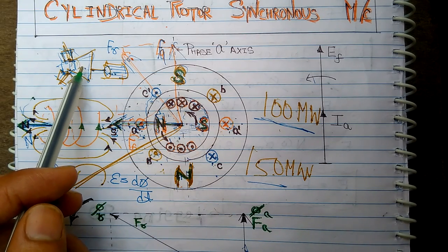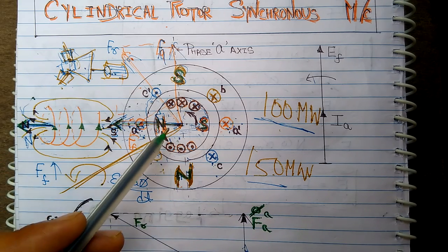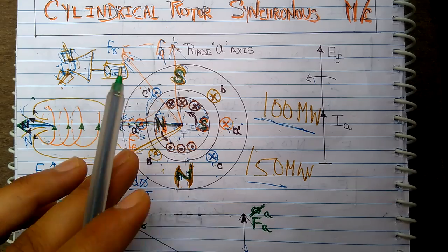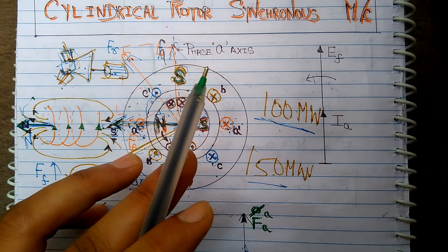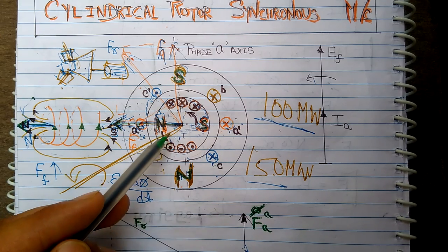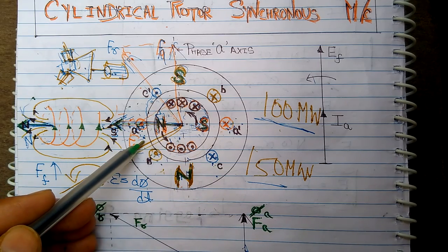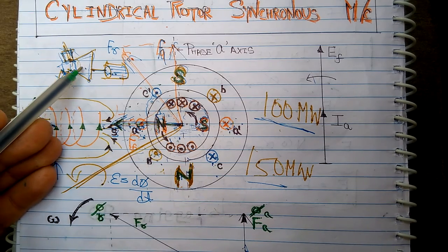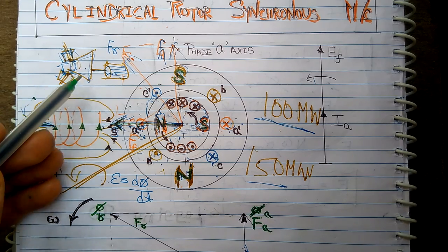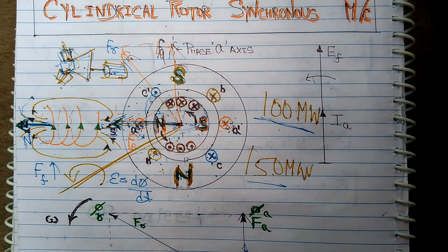You must have heard that the output frequency is controlled by the active power or the turbine. As the speed reduces, the frequency also reduces — you must have seen this in the synchronous speed lecture. But I put more steam on the turbine and increase the torque in the anti-clockwise direction, bringing the frequency back to its constant value — 50 Hz for the 3000 rpm case — so I am controlling the output frequency by the turbine.